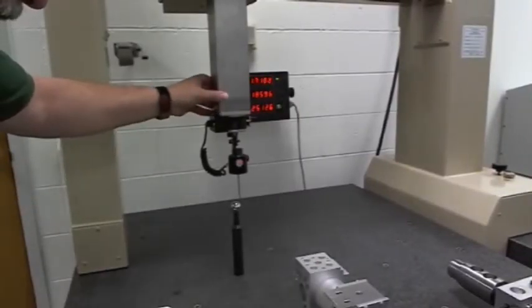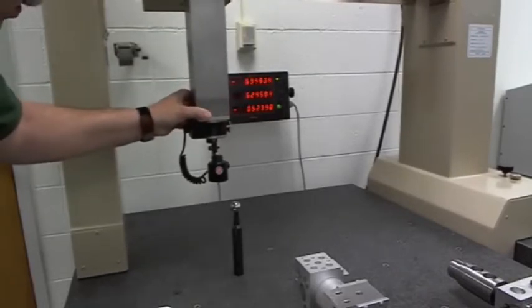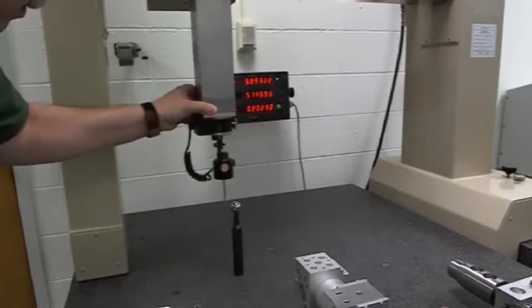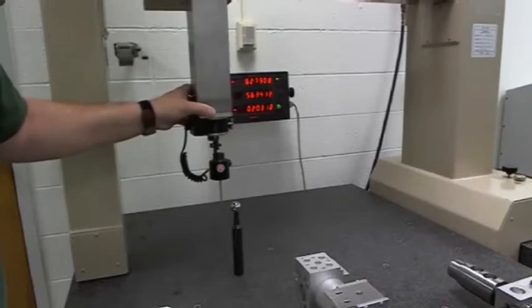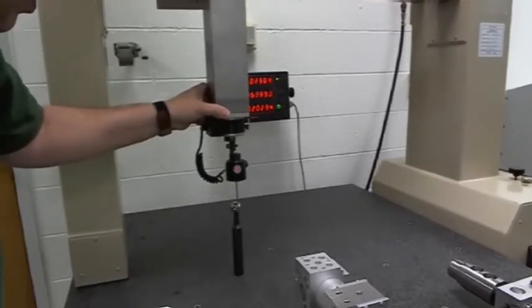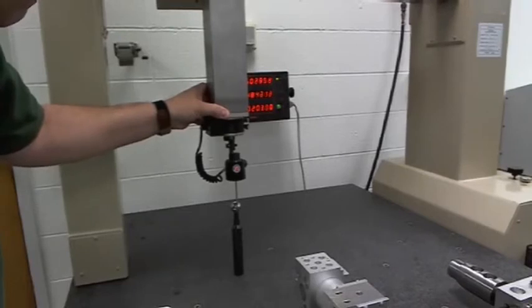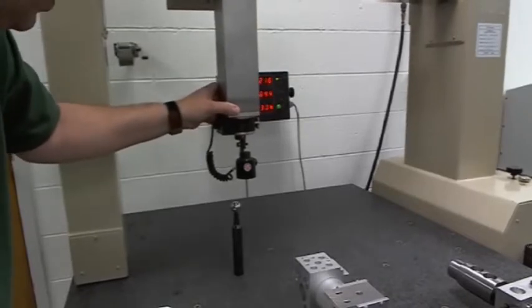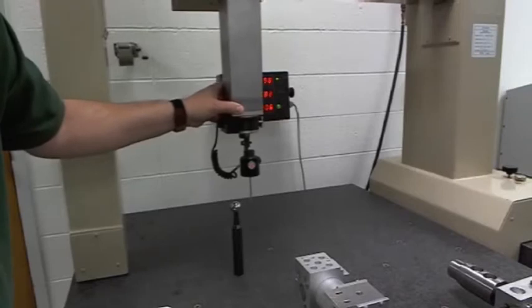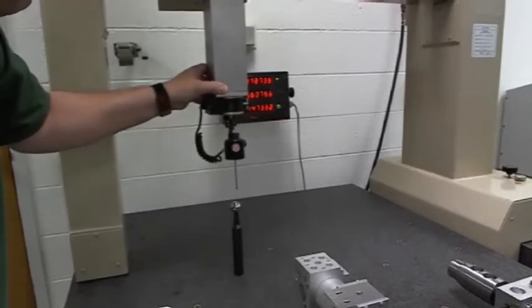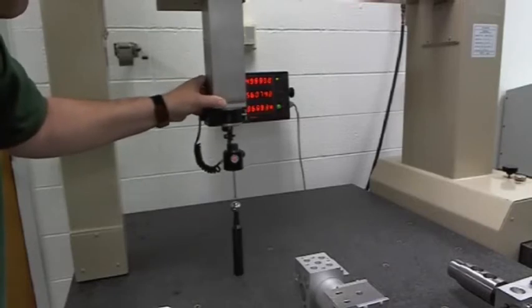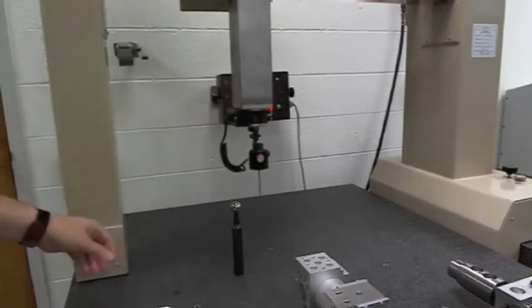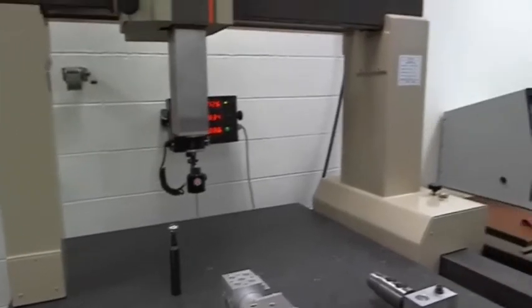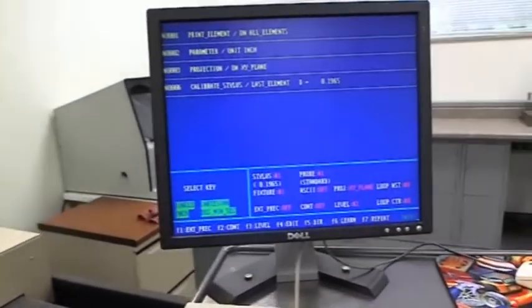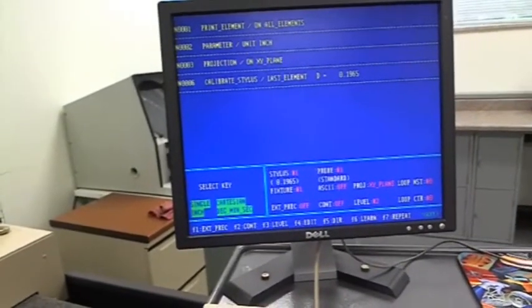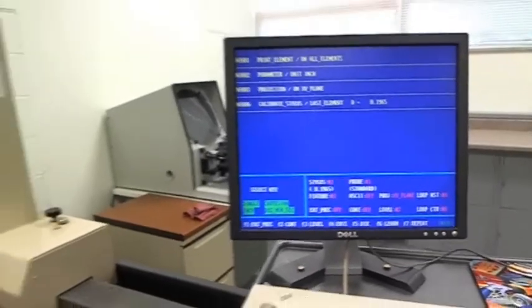Now we will turn on the probe. And then we'll catch the second point that's called out on the monitor screen. Then we'll get point 3. And then we'll go for point 4. And you'll notice that on the screen we have calibrated the stylus. Last element, D of 0.1965, which is actually the probe.